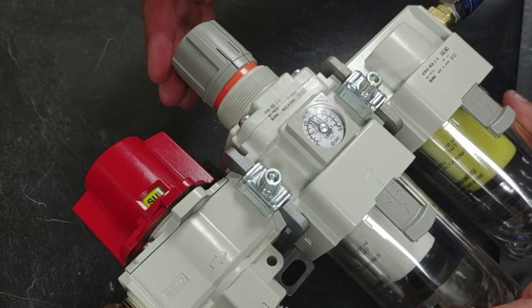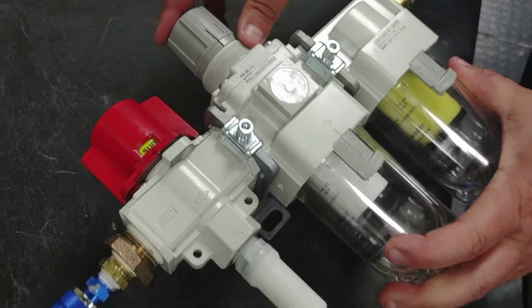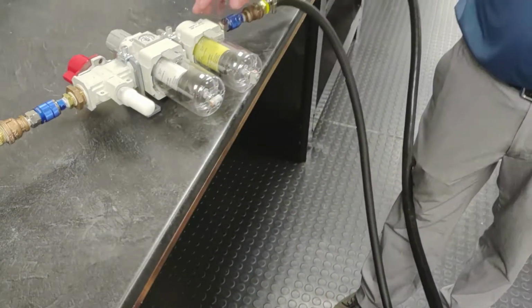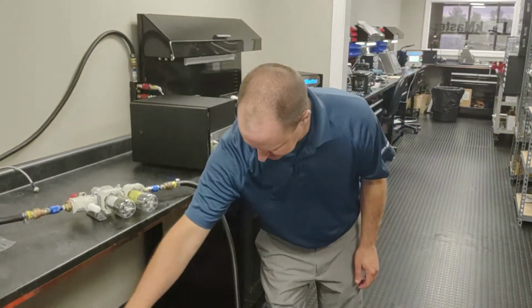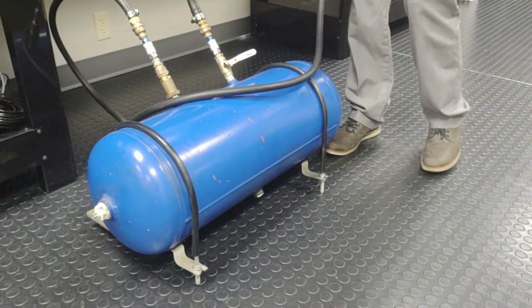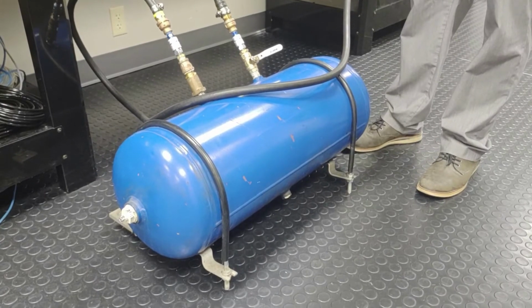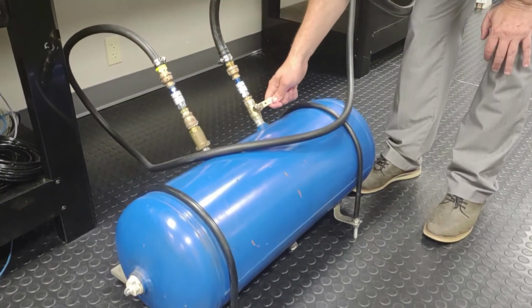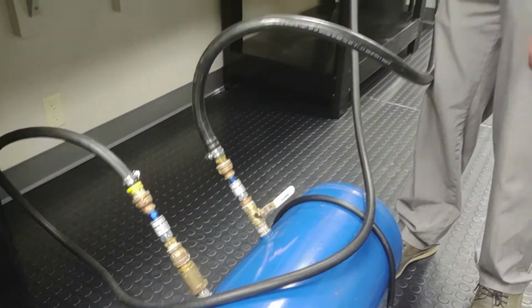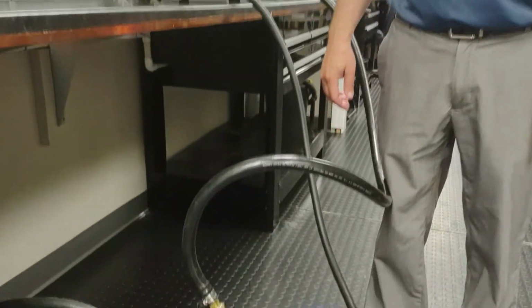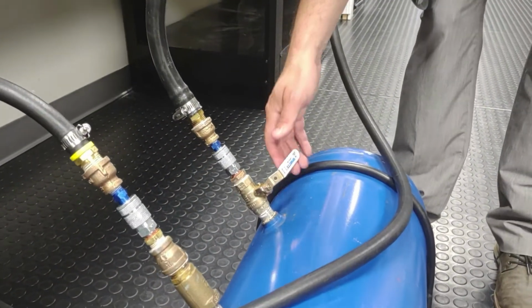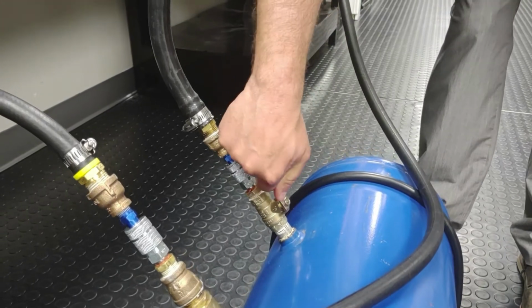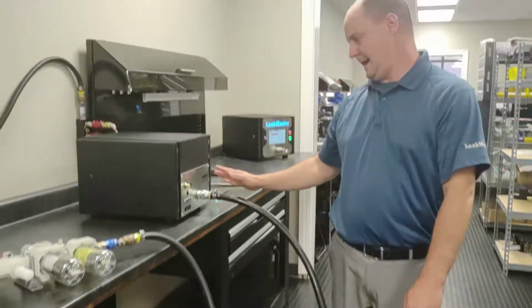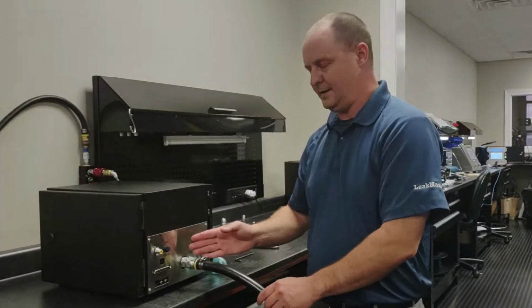Once I get it set to 60, I'm going to lock that in place so it stays put. So now we've actually filled this ballast tank up through our check valve. I can hear it's slowly filling. I've got a manual valve on the output of it, so I still haven't delivered air to the actual leak tester yet. So now we've got pilot pressure on, and we have air delivered to our unit.